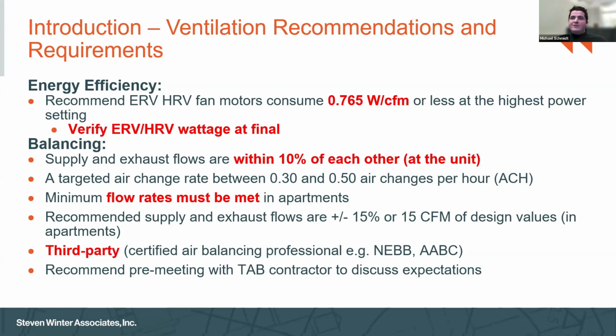To move on to balancing, this is a requirement outright. Supply and exhaust flows must be within 10% of each other. That's at the ERV unit. We are targeting a very specific air change per hour rate, and that's all for a reason and built into the standard now. I think it's also important to mention that we should really be targeting those minimum flow rates and meeting those within the apartments themselves, especially on the exhaust side. Again, if we aren't meeting minimum flow rates that are in the design, we can of course end up with issues, improper ventilation.